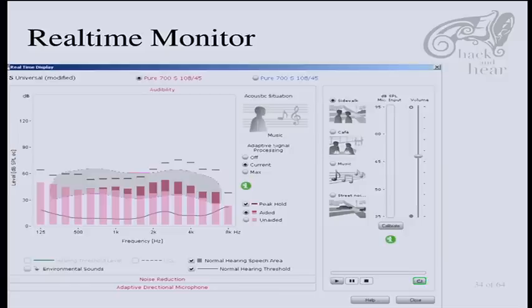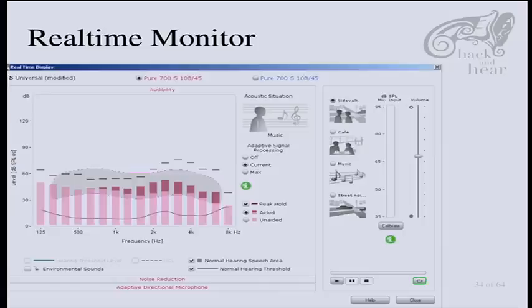The tuning software also has a real-time monitor where you can see parameters while wearing hearing aids — for example, listening to music. The dark areas show where the hearing aid actually started to work; below that it doesn't need to amplify. The grey area is the speech banana, so you can see it's optimized to start amplifying in the speech banana. It also has situation recognition in different settings, one of which is music. I tried it with different types of music — actually, if you like heavy metal, you will never see music recognized here; it's usually classified as noise.